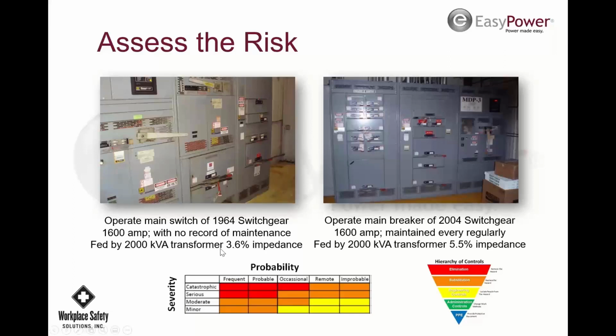I see that this transformer has a 3.6% impedance, and this one has a 5.5% impedance. So this is probably going to be 60,000 amps, and this is probably going to be 30,000 amps, somewhere in that range. So that's going to increase the available fault current. That available fault current is going to increase the arc flash level. So that's going to be where the feed comes into the main switchgear on either side, and that's going to have an impact. So now we're swinging back to the new switchgear again.